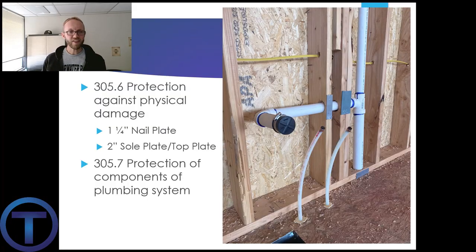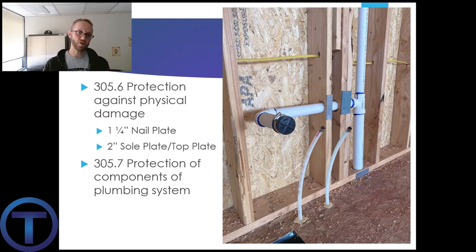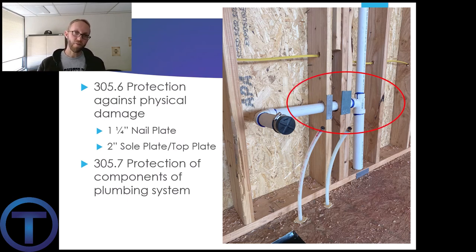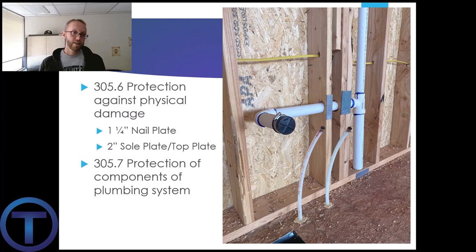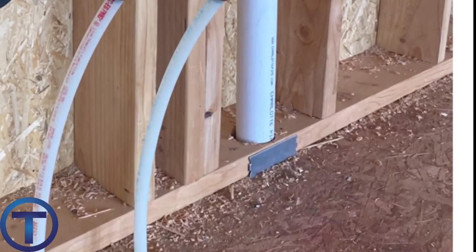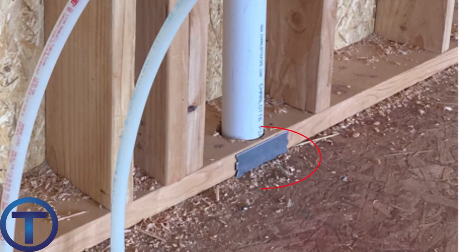305.6: Protection against physical damage. As they're hanging sheetrock on the wall, they're going to be driving screws into the studs, and those screws are long enough in many cases that they can penetrate right into our pipes. So we have to put on nail plates to protect the pipes from those screws. The requirement says that anytime the hole which the pipe passes through is one and a quarter inches or less from the face of that stud, we need protection. There should be a two-inch nail plate at the sole plate and the top plate — the sole plate at the bottom and the top plate running across the top of the wall.